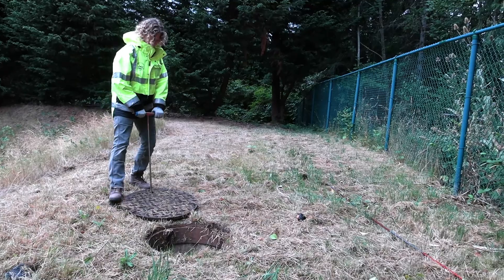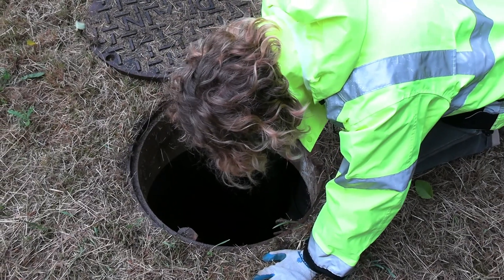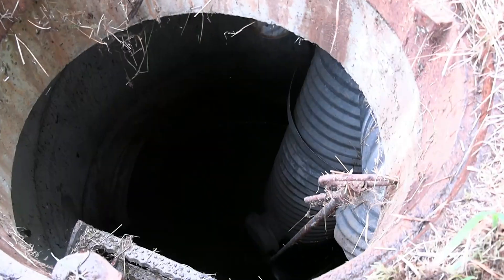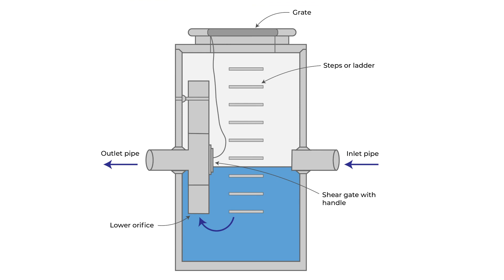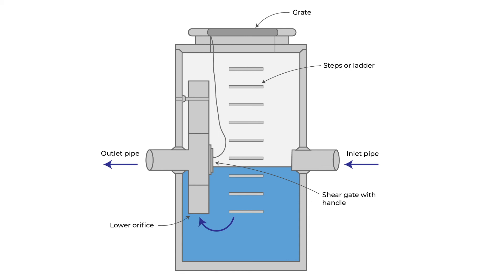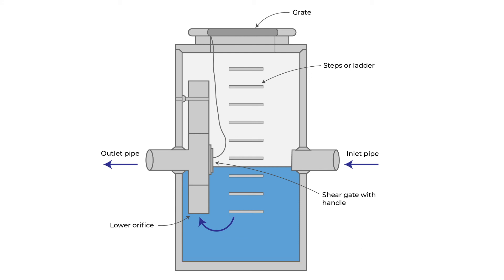Connected to the outlets of your pond, you'll find a control structure. The control structure is a large concrete vault or manhole and it contains a flow restrictor. The control structure acts as a final depository for sediment and pollutants before stormwater exits the pond. The flow restrictor is a vertical pipe that controls the rate that the water leaves the pond. Make sure that the control structure is free of debris and that the sediment does not exceed one-third of the depth from the bottom of the basin to the bottom of the lowest pipe. If the catch basin has cracks in the walls or the grout around the pipe is crumbling, have it repaired as necessary. Make sure that the orifice on the bottom of the flow restrictor is not blocked and that the shear gate opens and closes easily.